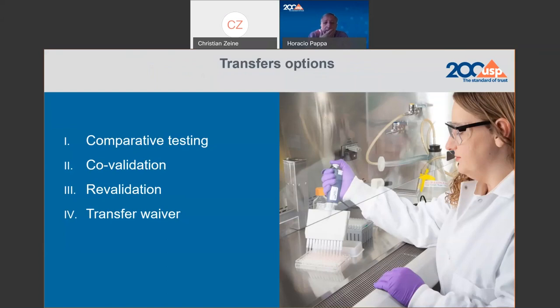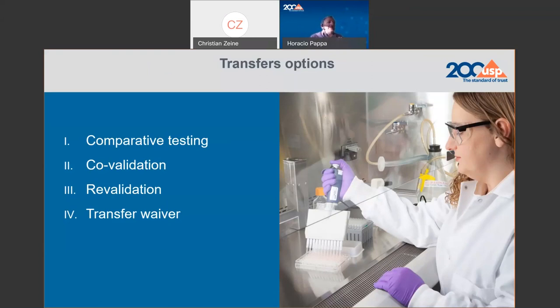Transfer is not an activity that is closely linked to a pharmacopoeial procedure, because if the procedure is in the pharmacopoeia, verification is the appropriate approach. Chapter 1224 was included in the pharmacopoeia to close the loop between all activities related to the generation of analytical data. There are four approaches for transfer: comparative testing, co-validation, revalidation, and transfer waiver.